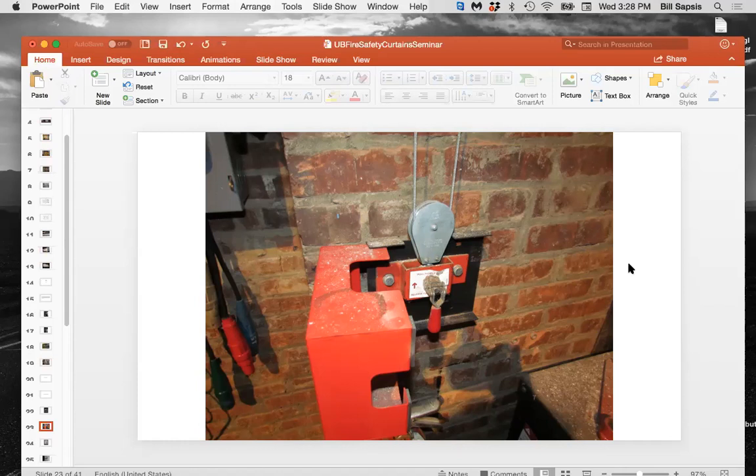This flap hanging down will seal that opening, because as the hot air tries to come up, it will push the flap up against the fire curtain. And if the seal is long enough and it goes all the way across, like 2 feet wide and all the way across the proscenium, it will trap the air and not allow it to come up and over the top of the fire curtain.